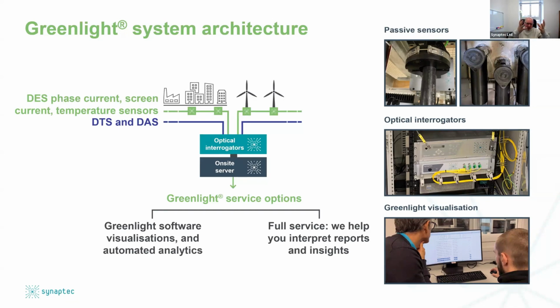And all of the electrical sensors, and indeed DTS and DAS information, is all brought back to a central point. So you've typically got a cabinet at a central location where we're building up that data history of information about what's happening with that asset over time. And again, permanent, synchronous monitoring of all of those measurands. And that's the clue. At that point, we can serve up data. And some customers have said, just please give me the data. I know how to absorb that data into SCADA and make sense of it. But actually, there's so much data and there's so many correlations that we're looking for.